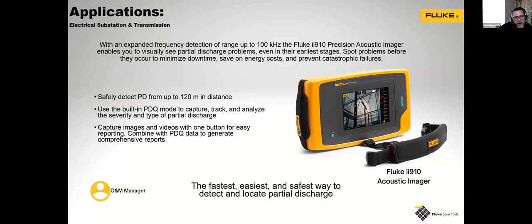Okay. So just a quick note on the II910. It's got 100 kilohertz frequency range. You can spot partial discharge from 120 meters. 120 meters, just to give you an idea, is so far away that you know that it's somewhere in the distance. So we have found, and I have found 120 meter partial discharge, but you tend to have to get a little closer to it to start localizing it, but you can detect it from 120 meters.